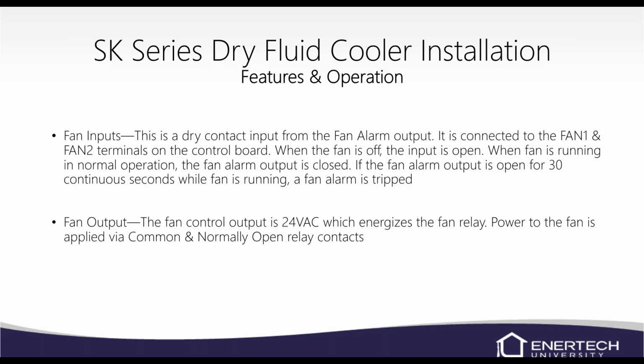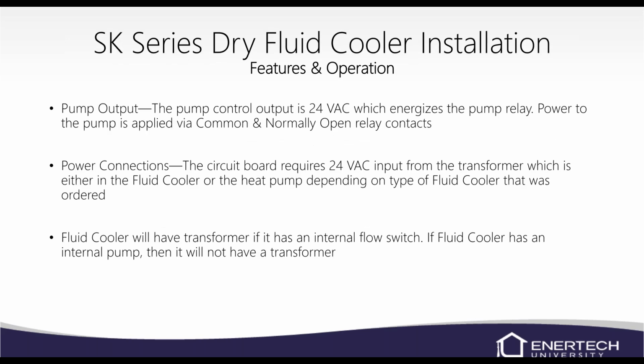Fan output, the fan control output is 24 volts AC, which energizes the fan relay. Its power to the fan is applied via common and normally open contact on that. So once it gets 24 volts, it will start up your fan. It does have a pump output. It's a pump control output. So again, it's a 24-volt AC signal, which energizes a relay for the pumps. And again, it's the common and normally open contact. So the power closes the contact and tells the pump to run.